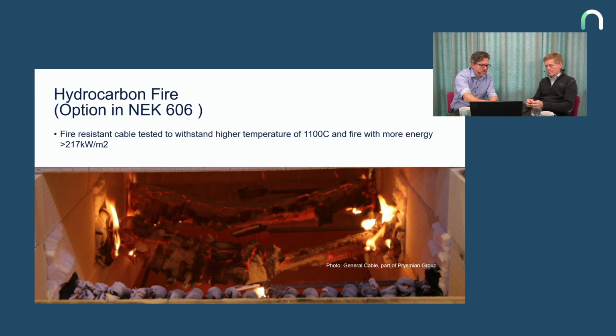It doesn't look like there's much left. No, it's a frightening view, yes. So this picture is after the test. You can see all these plastic parts are more or less burned away, and it's only the inorganic parts and the metal left in this case. But if the cable passes the test, it is still working and transmitting power, transmitting data. I think it passed the test, this one.